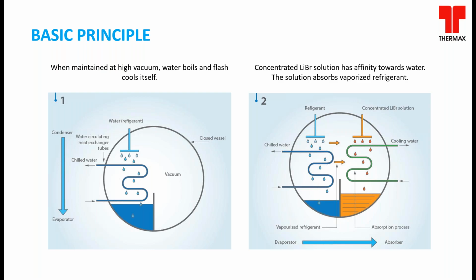Now, for those of you who are new to this technology, you should understand that this entire operation happens under vacuum. Why vacuum? Because we are using water as refrigerant. You might know water boils at 100 degrees Celsius at sea level. As you go to higher and higher pressures, the boiling point increases. Similarly, when you go to lower and lower pressures, the boiling point decreases. This is the fact that we are utilizing in this absorption chiller. So when you maintain a very low pressure inside the absorption chiller, we can evaporate water at as low as 3 to 4 degrees Celsius.